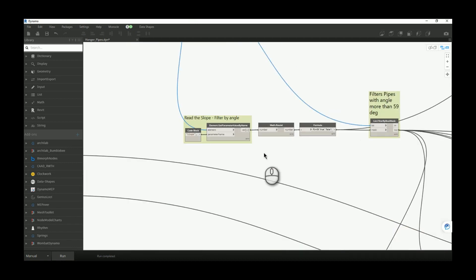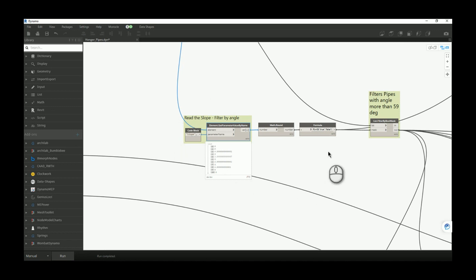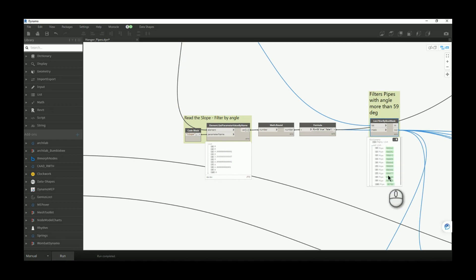I want to read all slope values for my pipes. If I detect a slope value greater than 59 degrees, I will consider that pipe to be a vertical pipe and will not place a hanger on it — that is why I created this logical condition. I will have a filter here. Because my maximum slope is four degrees, I will have an empty list in the filter and I will pass the entire list of pipes to the other nodes.